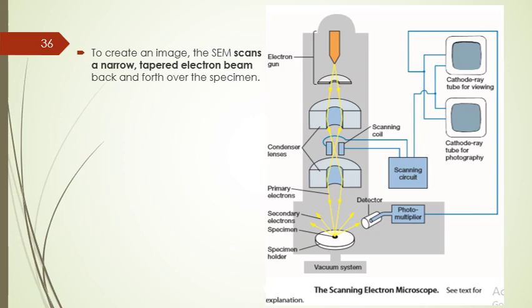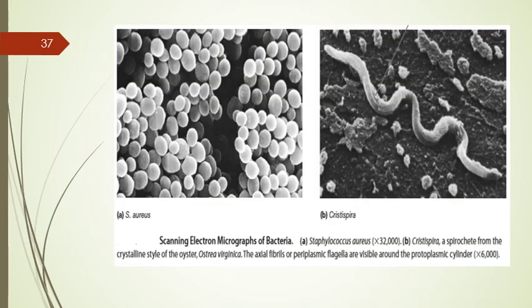The number of secondary electrons reaching the detector depends on the nature of the specimen surface. When the electron beam strikes a raised area, a large number of secondary electrons enter the detector. In contrast, fewer electrons escape from a depression in the surface, so raised areas appear lighter on the screen and depressions appear darker. Examples of SEM images include Staphylococcus and Cristispira.